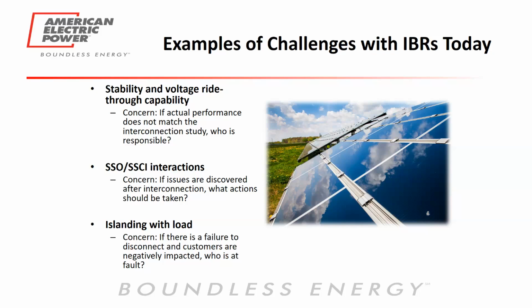We have a situation now that we're working through where we're seeing issues with an interaction of a nearby plant with a series capacitor. The solution, temporarily, is to take that series capacitor out of service under normal operation. So it's one of these things where we're having to reconfigure the grid based on an issue that really should have been addressed by the plant and uncovered through the interconnection study, but for one reason or another wasn't. Maybe it's a modeling deficiency, whatever, but now whose problem is that?